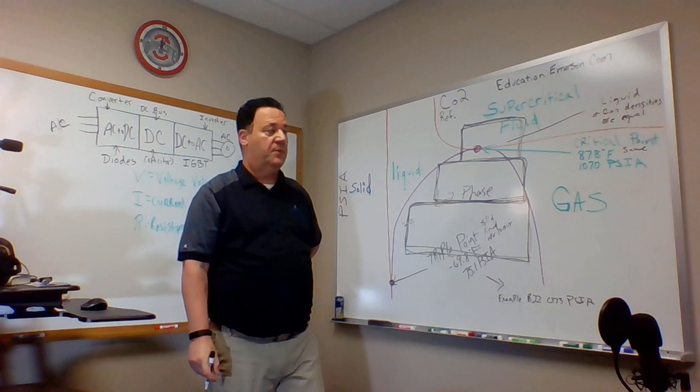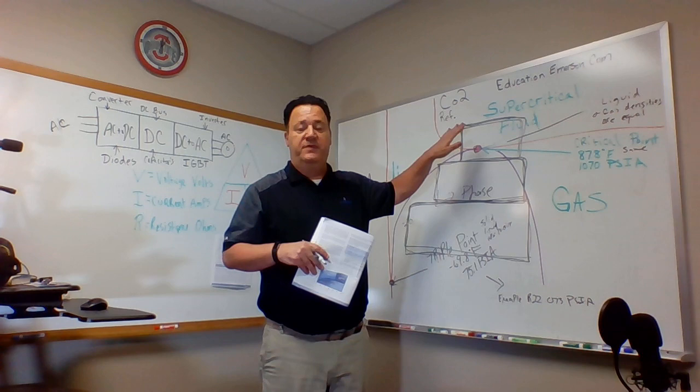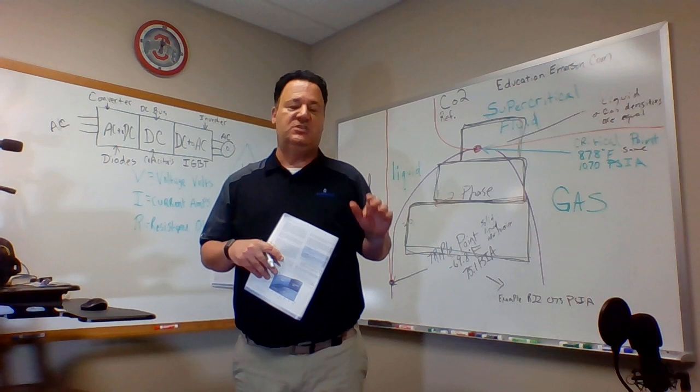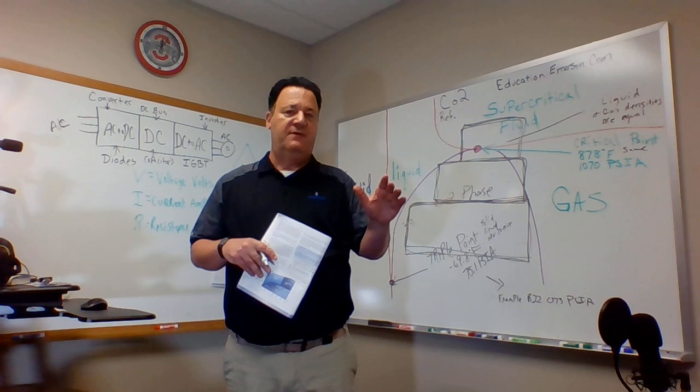Pressure temperature no longer exists here, relationship-wise, all right? That is neither a liquid nor a vapor above the critical point. It is referred to as a supercritical fluid. Now, I don't want to get too far ahead of myself, but the condenser, we can't condense the refrigerant at that point, above that critical point, basically is what it amounts to. So it never condenses, all right?